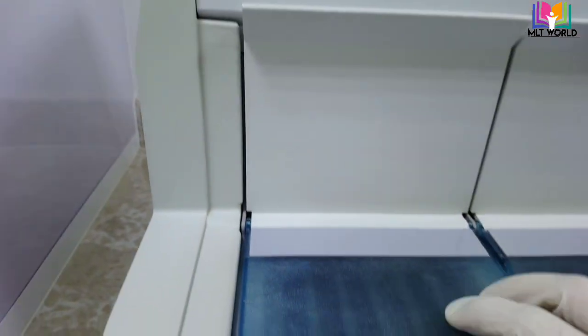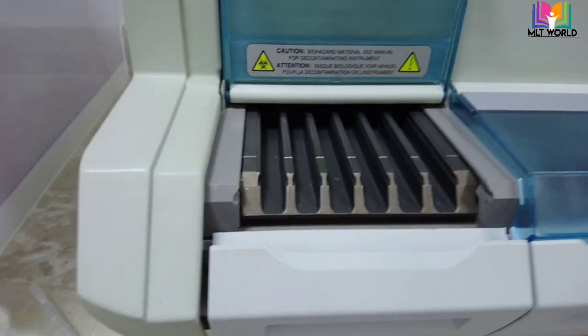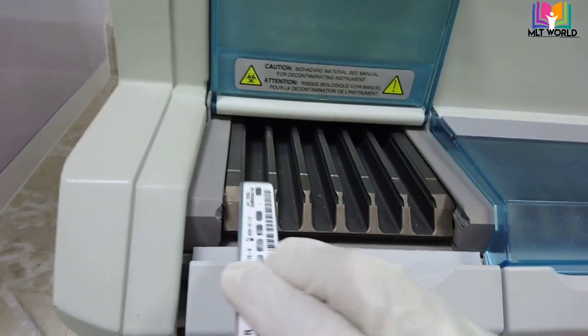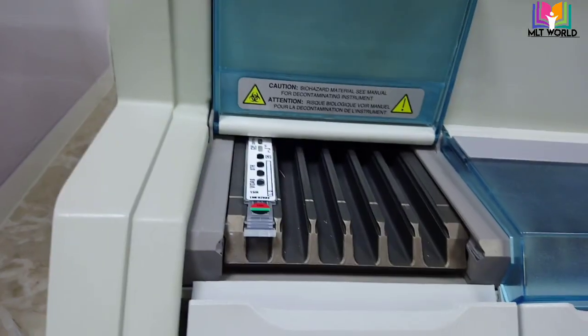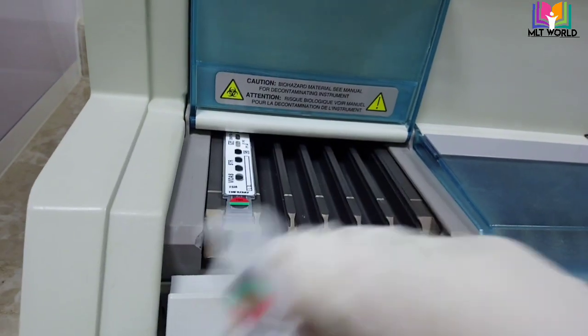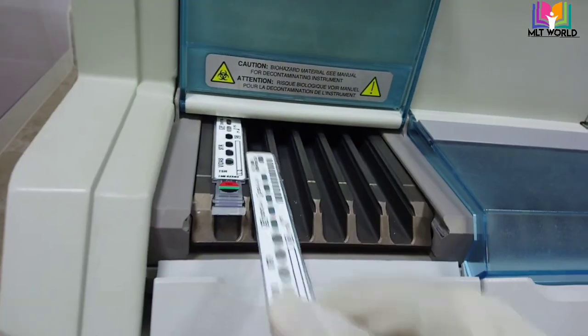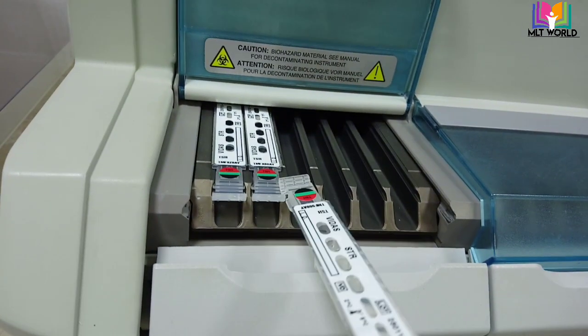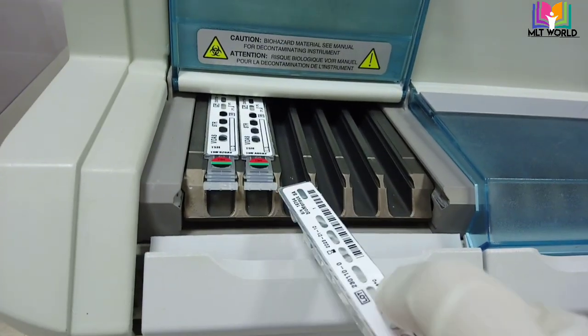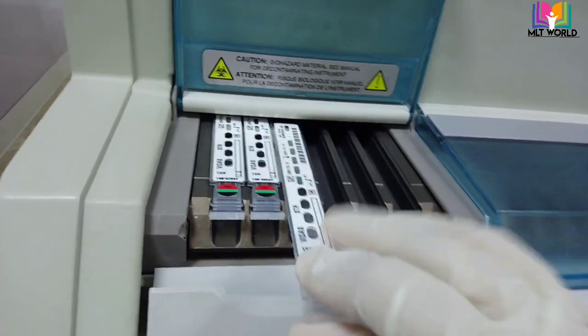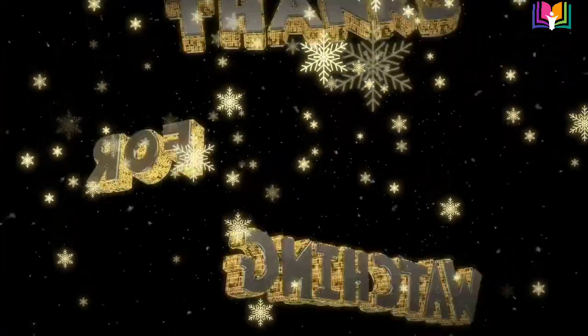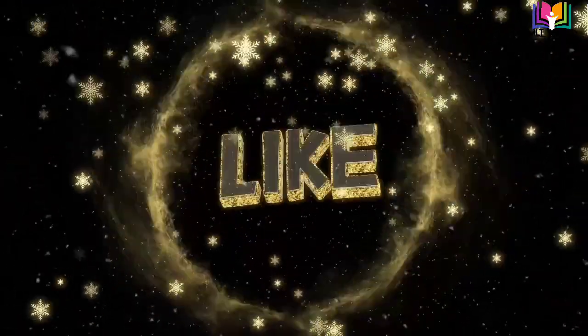So for newcomers, I think this video will be helpful, on how to read the MLE card in the Vidas analyzer. For any kit, the MLE card reader procedure is the same. If, for example, a new kit is coming that has not been entered in the machine, then first you have to go into the configuration and do the assay activation. After that you will read the barcode for the calibration.